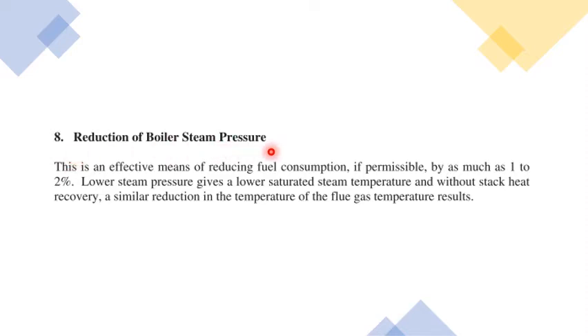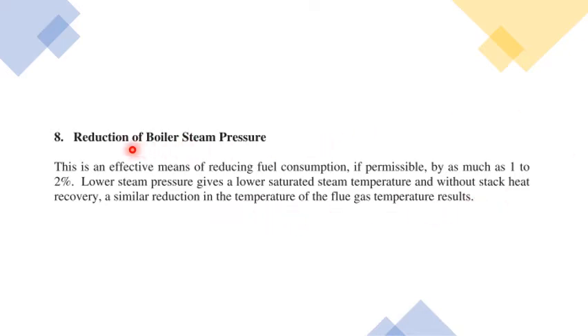The eighth point is reducing boiler steam pressure. In many industries, the steam pressure generated is higher than what is actually required. If you can reduce the steam pressure by even 1–2%, it leads to better boiler efficiency. Lower steam pressure gives a lower saturated steam temperature and a similar reduction in flue gas temperature. Unnecessary excess steam pressure generation only leads to energy loss.